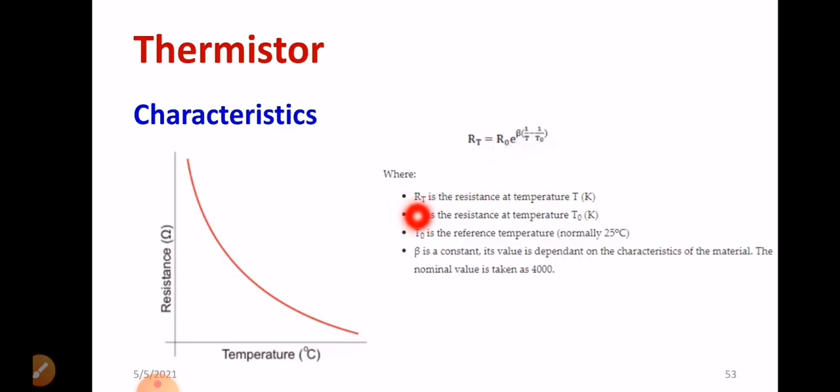What is RT? RT is the resistance at temperature in Kelvin. What is R0? Resistance at zero temperature. T0 is nothing but reference temperature, normally we consider 25 degree Celsius. If you want you can convert to Kelvin also, 25 degree Celsius plus 273. Beta is a constant. Its value is depending on the characteristics of the material. Beta will be directly depending on what type of material you are going to employ. I have given the checklist of material which will be used in the thermistor. The normal value is taken as 4000. That is the peculiarity.